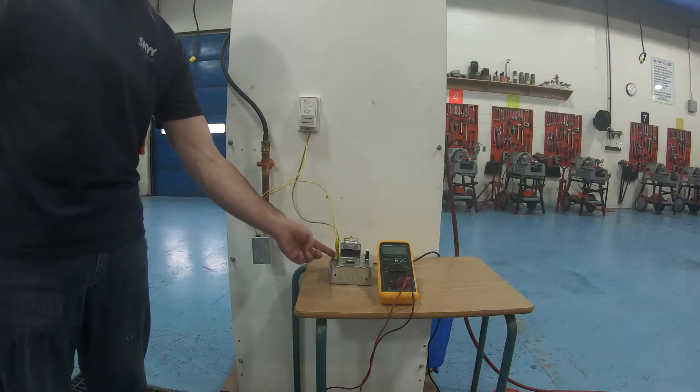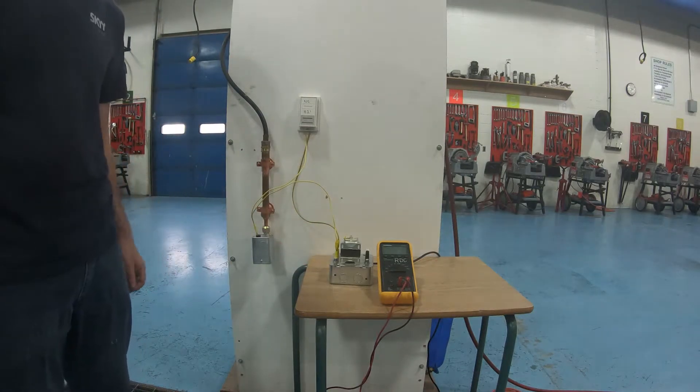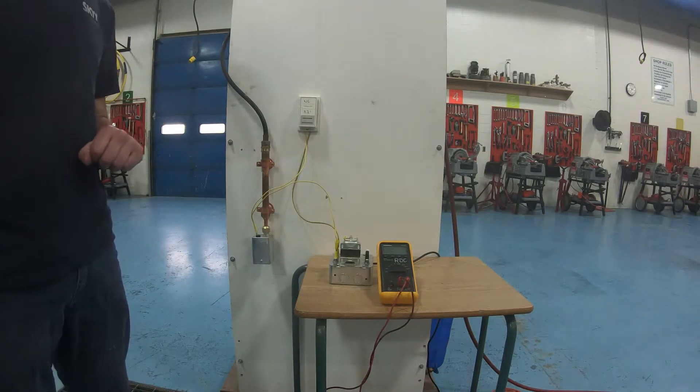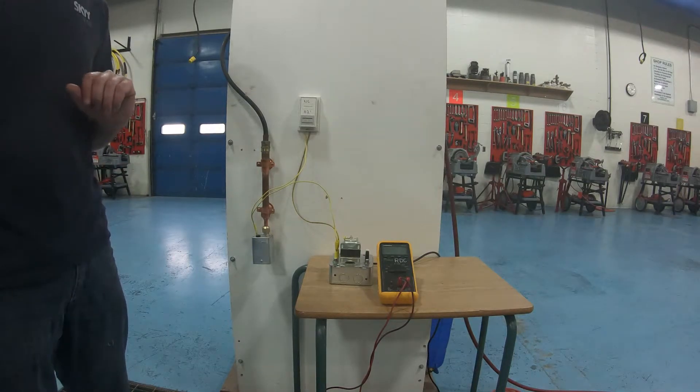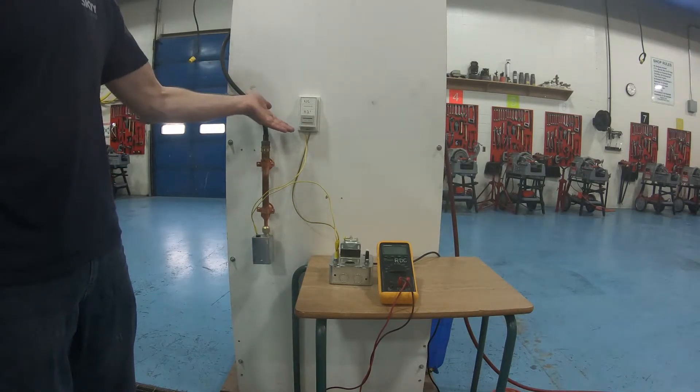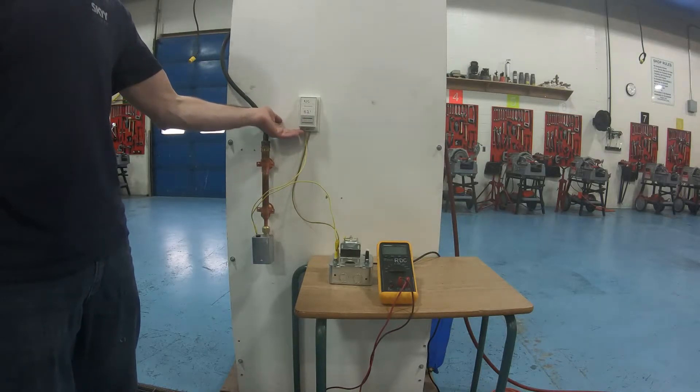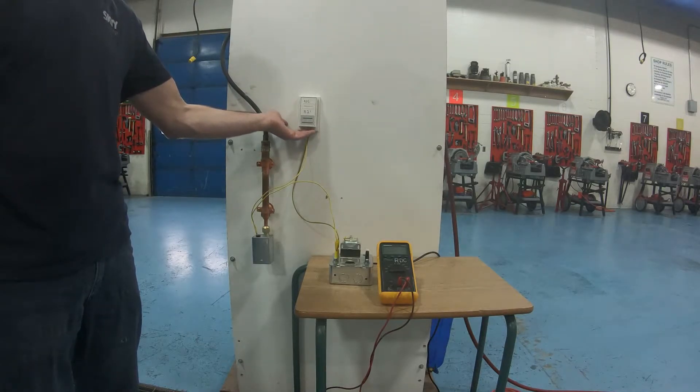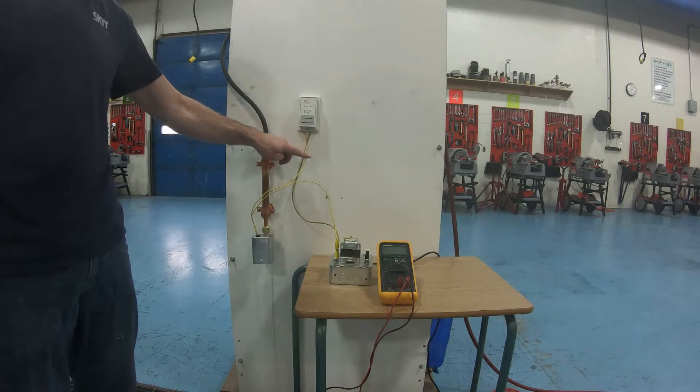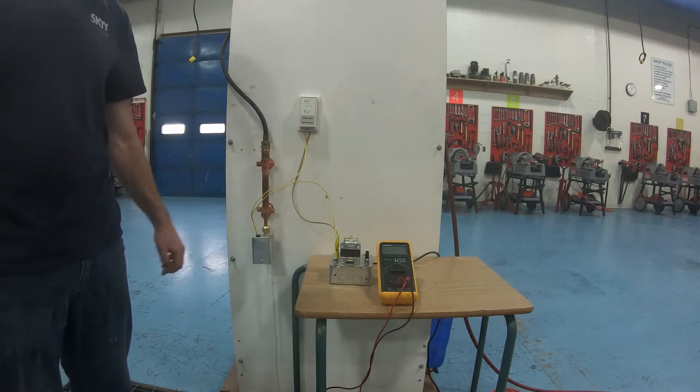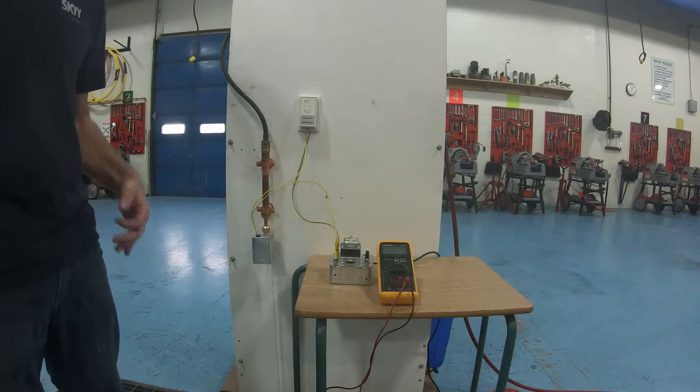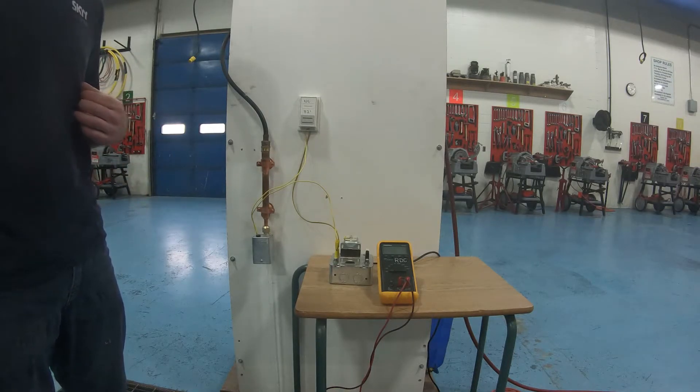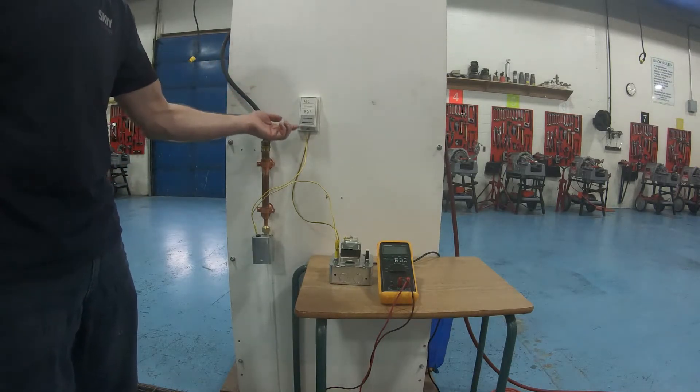And this comes down the other side of the switch to the zone valve. The other wire for the zone valve needs to come to the other side of the transformer to complete the circuit. Right now this zone valve is powered down, so it's closed, normally closed. So I'm going to take my normally closed thermostat and turn it all the way up. So now power is coming through here, opens the zone valve and water starts running out. Typically that would be run into a piping system, but that's not very good for demonstration purposes. If I turn the thermostat down, the valve shuts.